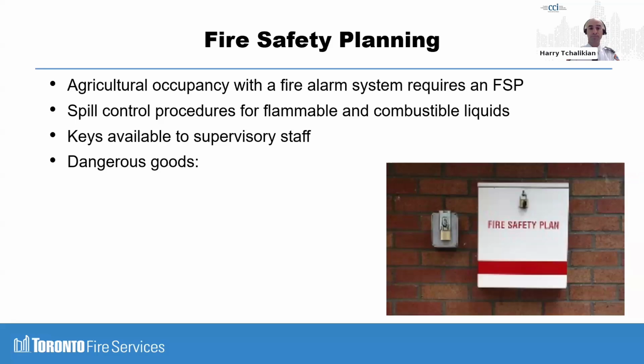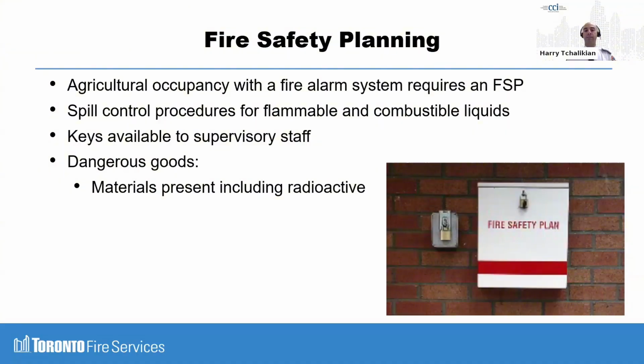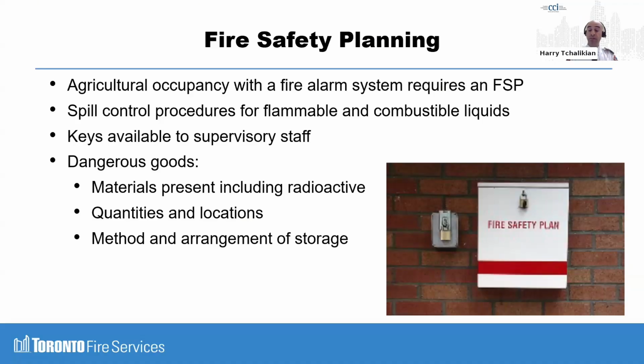Next, dangerous goods. So dangerous goods, materials present including radioactive, which would apply to industrial facilities and hospitals, not so relevant for residential. What needs to go in your fire safety plan? Quantities and locations. How much do you have and where is it? Method and arrangement of storage relative to the hazardous material. Emergency contacts and procedures. There needs to be contact information for 24 hours, the address, name, and phone number of the person who's responsible for handling your dangerous goods. It could be the superintendent. You also want to have CANUTEC's phone number in there.